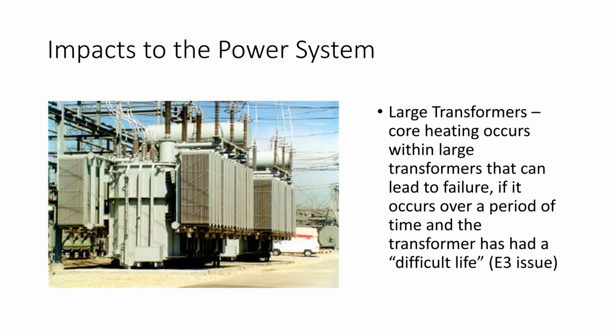I would be remiss if I didn't talk about large power transformers here. We have a picture of one of those on the left here, and you can appreciate the size of this. There's basically a full-size van sitting behind it here in the picture. These are massive, massive devices on the power system. And I mention this because I talked about E3 and the fact that the slow pulse, the pulse of the E3, is such that it's in a time domain where it starts to cause core heating in transformers. The transformer is basically large amounts of metal that are magnets with two coils of wire, and basically they're used to either step up voltage or step down voltage. The transformer looking at here is a large one, but pretty indicative of the kind of large transformers you see in substations. In the EMP event, they are likely to face core heating based on the pulse itself.